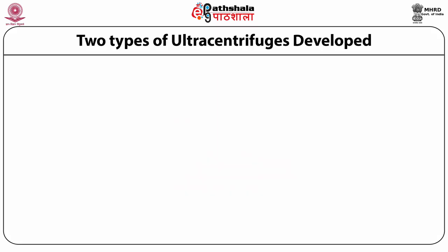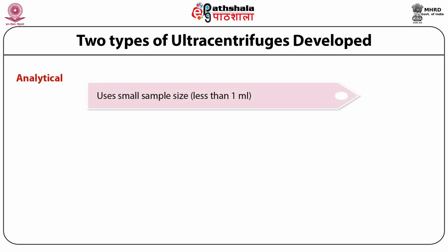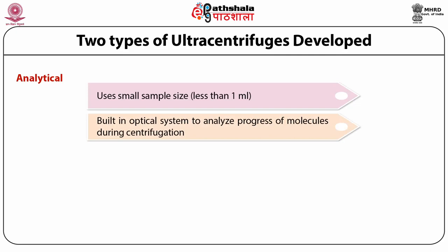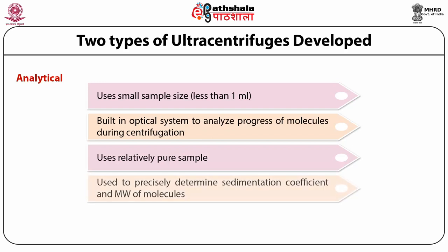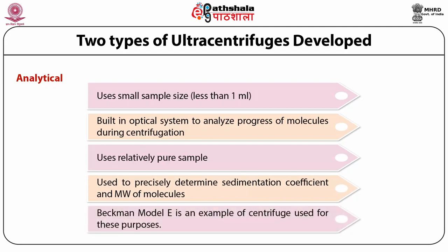Ultracentrifuges are divided into two categories: the analytical ultracentrifuge and the preparative ultracentrifuge. The analytical ultracentrifuge uses a small volume of less than 1 ml and has an inbuilt optical system to analyze the progress of molecules during centrifugation. It uses relatively pure samples for measurement of biophysical properties and characterization, and precisely determines sedimentation coefficient and molecular weight. One example is the Beckman Model E.